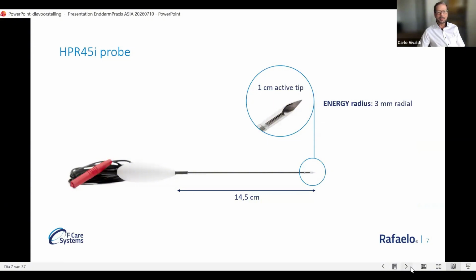So the probe is an almost 15 centimeter long metal probe, which is good because it's resistant, it's steel, so not easy to bow on one hand. On the other hand, you can target it very well to your position where you want to insert the tip. And the tip itself is only 1 centimeter active. We have an isolation ring, which is a plastic ring. You see it here in the magnification. And from there on, the probe is not isolated, so the energy will flow in the last centimeter. So the rest of the probe is covered, so safe. And as I said, the radius as it worked is 3 to 5 millimeters, so very controllable. Next.